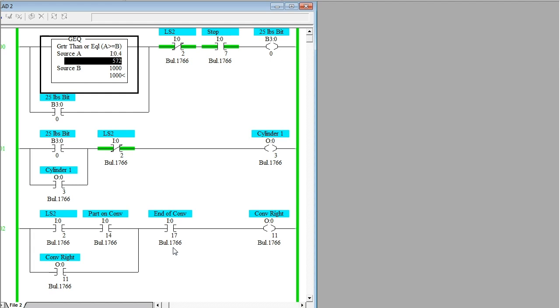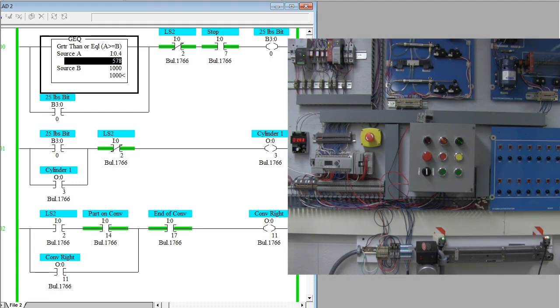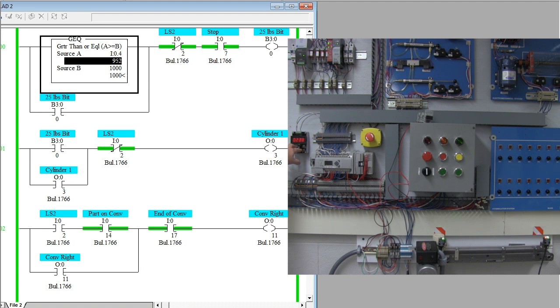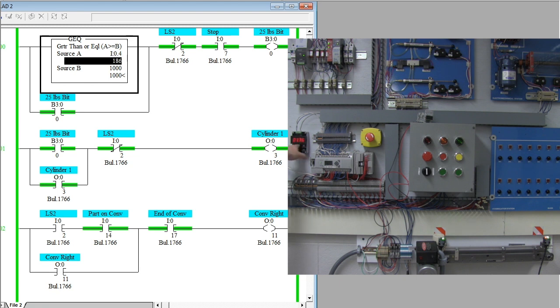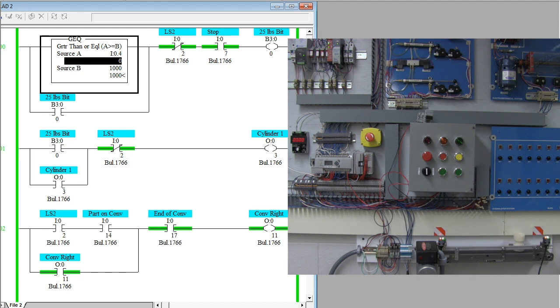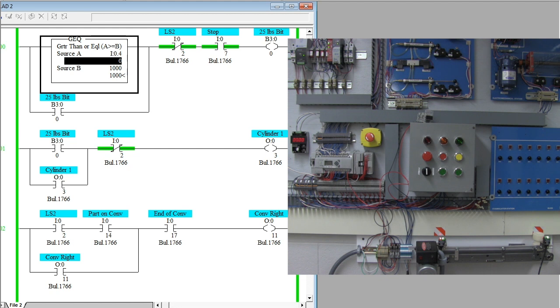Let me go ahead and show you how this works. I'm going to activate the analog signal as if more grain is being put onto the strain gauge, and once it reaches 25 pounds it will send a voltage over to the PLC which will be interpreted as a thousand. The cylinder is activated. Now the weight immediately drops back to zero, the cylinder extends, it activates LS2, and then the conveyor activates until it gets to the very end and turns the conveyor off.